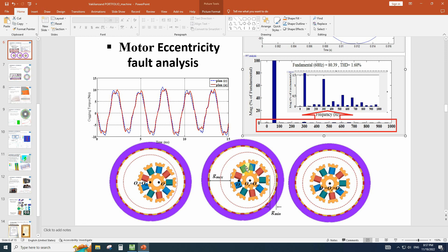One is named static eccentricity and the other one is dynamic eccentricity. In the static eccentricity, the center of the rotation is equal to the center of the rotor, but the center of the rotor and the center of the stator are not the same. We have a displacement between the center of rotation and the center of the stator.